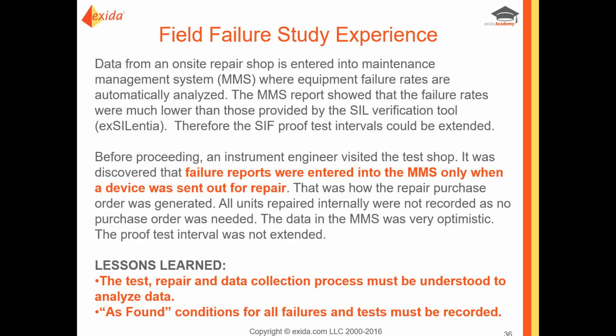Wow! No wonder it was optimistic. The proof test interval was not extended, fortunately. And again, the lesson is we must understand the data collection process and the as-found conditions.